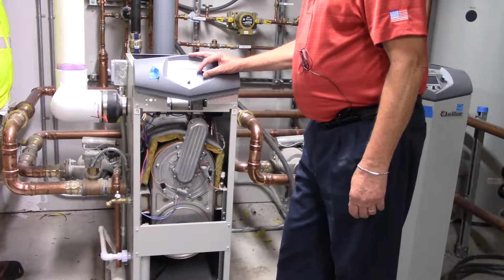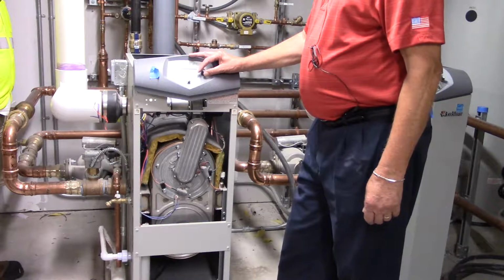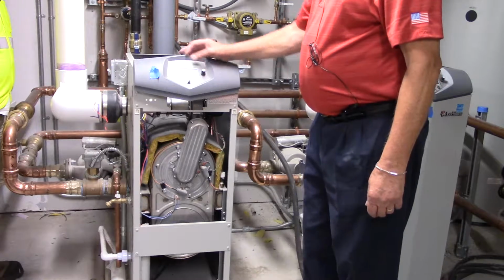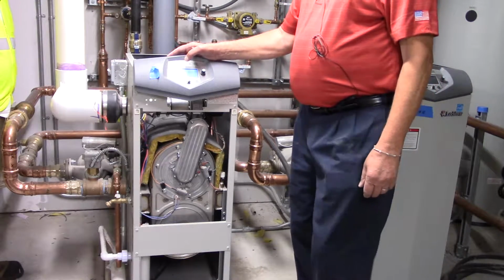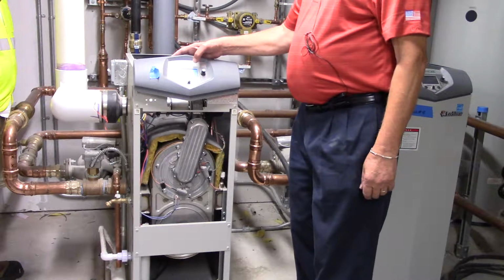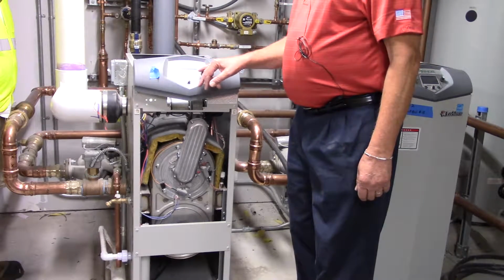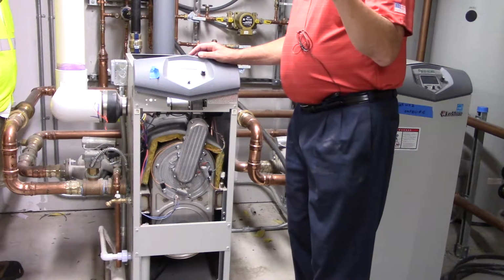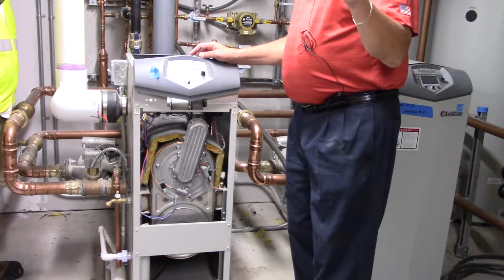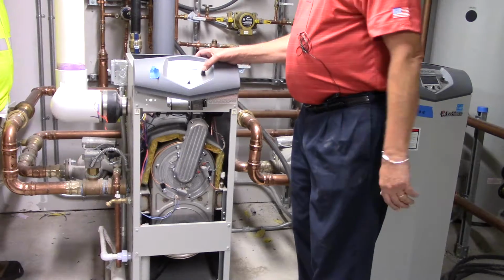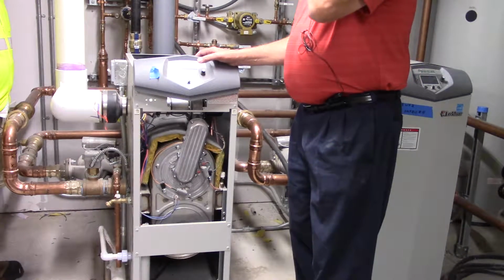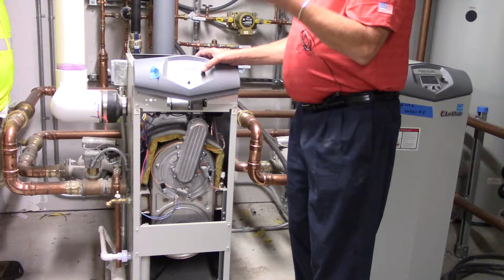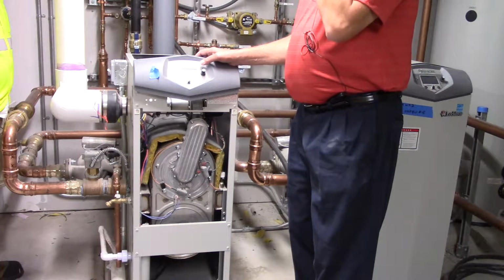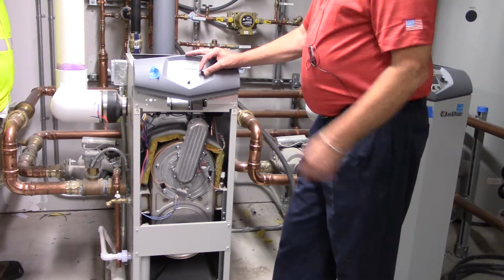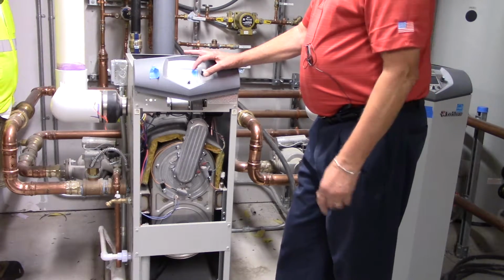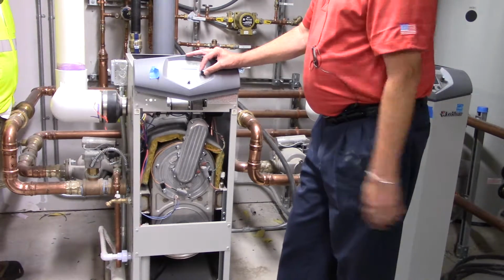You can get the number of run hours and the number of cycles off of this screen. And there is a fault screen. When you flip it through to the 5th screen, it'll say last 10 faults. So it'll give you fault number 1, like if it's flame failure ignition, and then if you hit this button down, it'll go to number 2, if there is a number 2, etc. 3, 4, 5, all the way through. So that's good information for you to have. That's going to be what shows up on the screen when it's red.